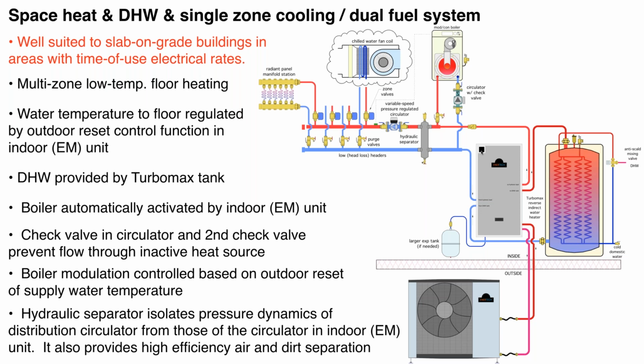And the piping here, basically what I did is I took the previous piping diagram and I just added that boiler in parallel with the indoor unit of the heat pump. So again, we have a circulator built into the indoor unit that's going to provide the flow up through, and you'll see there is a check valve there, over to the hydraulic separator and then back into the indoor unit. And of course, this circulator then takes it from there and sends that fluid off to whatever zones are open.